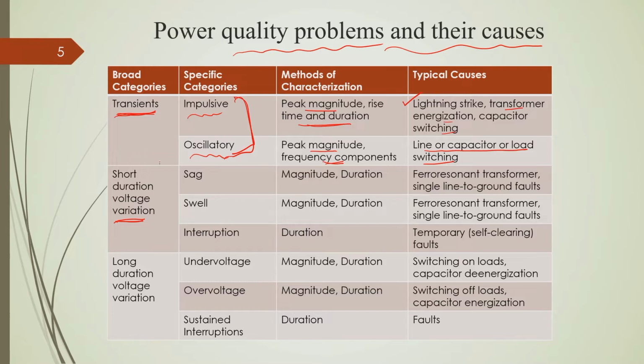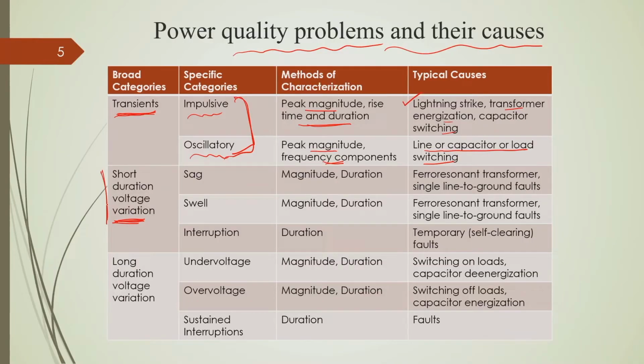For short duration voltage variation, the typical period of occurrence is very short, from within a few cycles up to 1 minute, that is, from a half cycle to 1 cycle up to 1 minute. So, this kind of problem sustains for a very short period of time. But I will discuss the impact of those short duration power quality problems, which is not short; the impact will be a long duration problem. That is why their mitigation at the time of occurrence is very important. So, those things we will discuss.